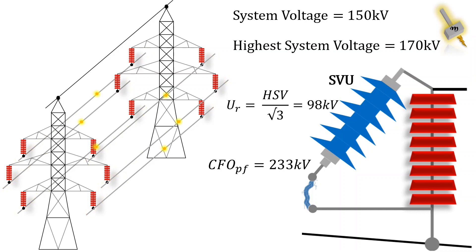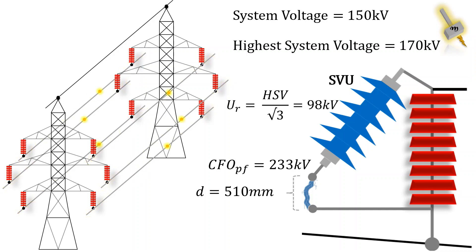The critical flashover voltage at power frequency level will be 233 KV. For that, the minimum spark gap distance will be 510 mm.